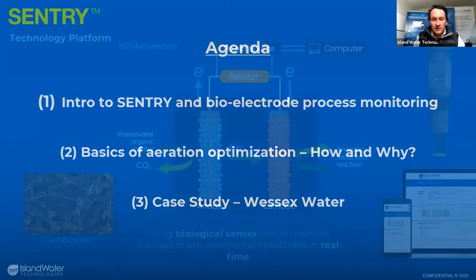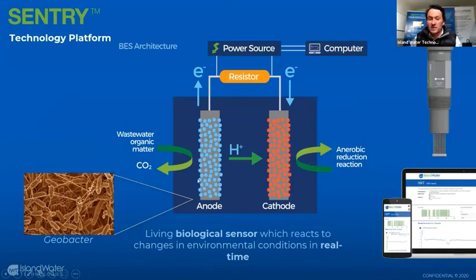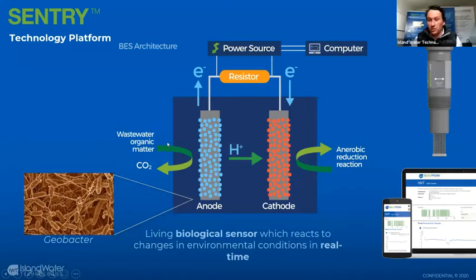So what is Sentry? Sentry is a novel technology where we grow active biomass on conductive surfaces and apply a very small voltage across two conductive surfaces. This allows the active biology in your wastewater treatment process to grow on those surfaces. That biology consumes the exact same bioavailable carbon that other microbes in your bioreactors consume. The key difference is in their respiration — these microbes donate their electrons to the surface rather than to oxygen or CO2. We measure the flow of those electrons, providing both a measure of the rate of carbon consumption and the metabolic activity of that biomass.